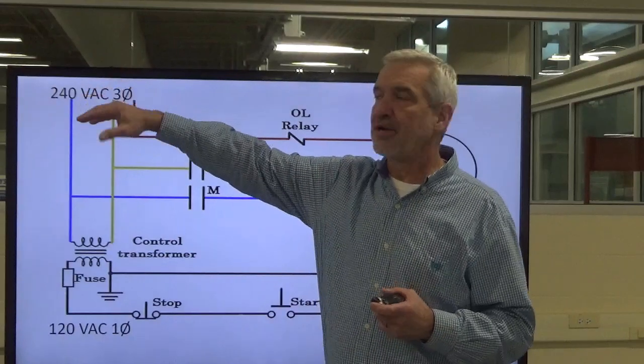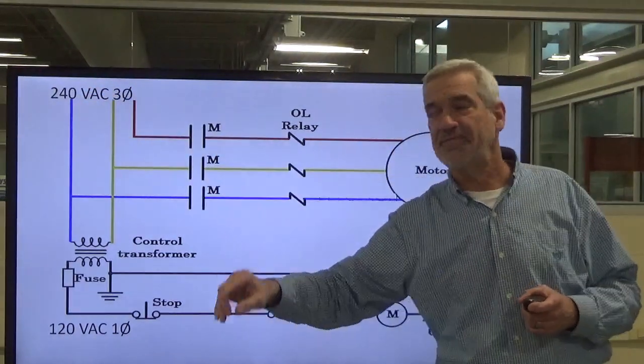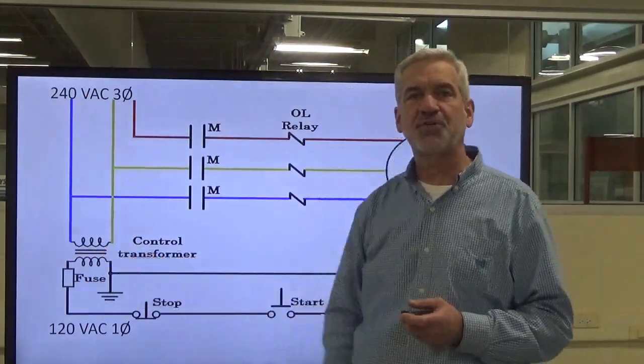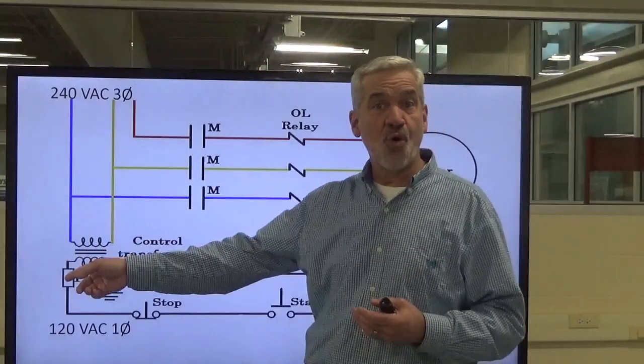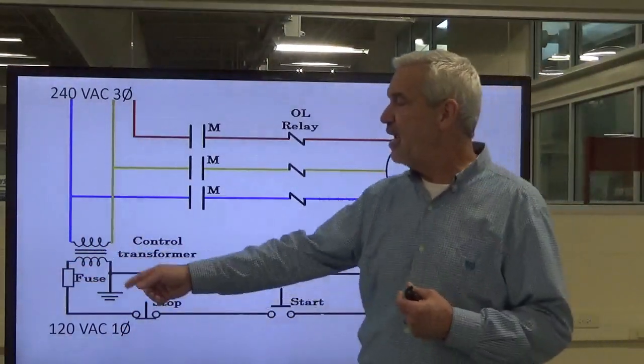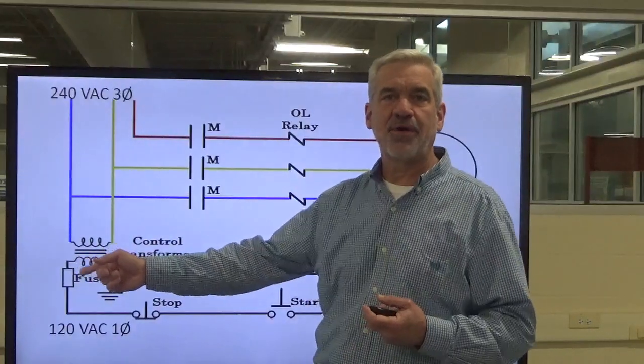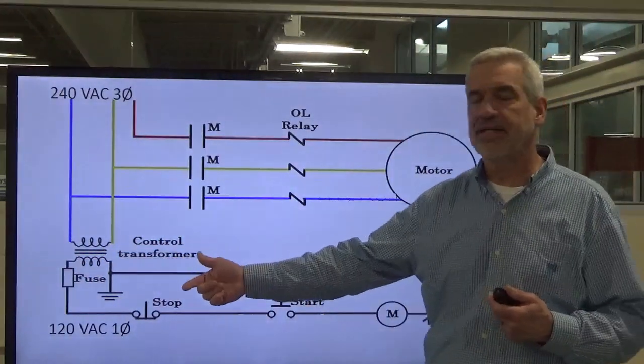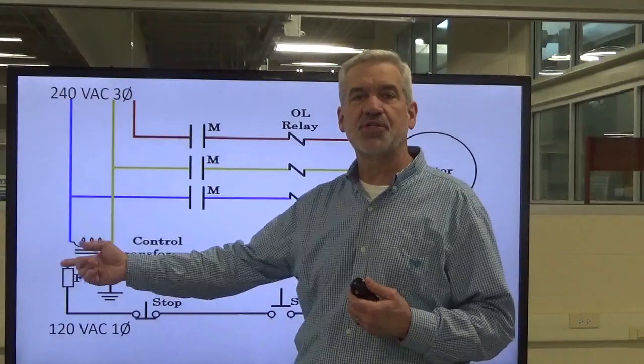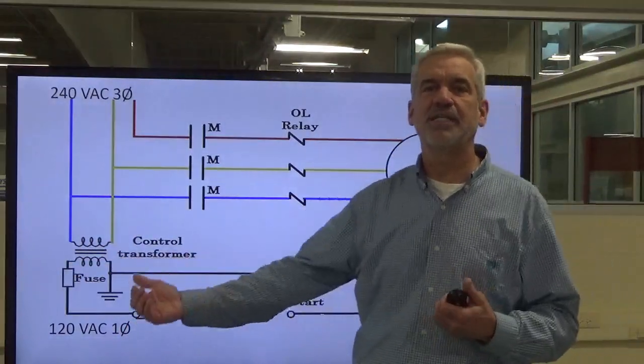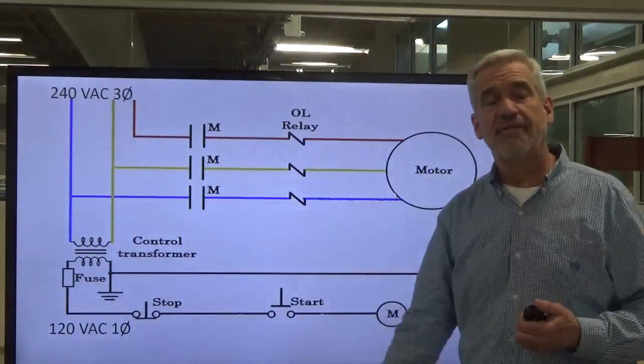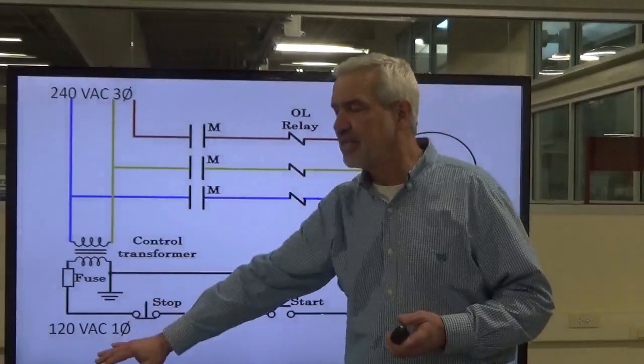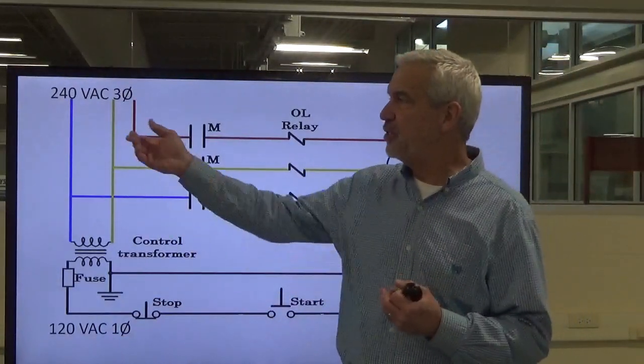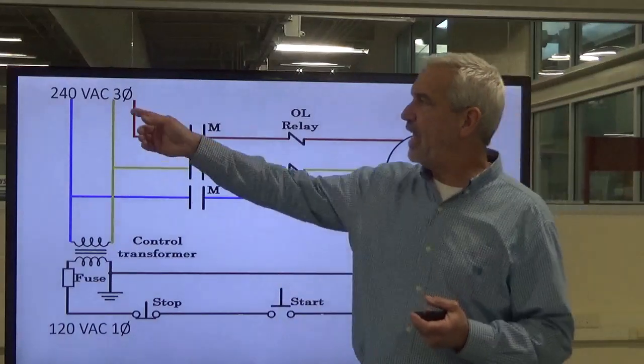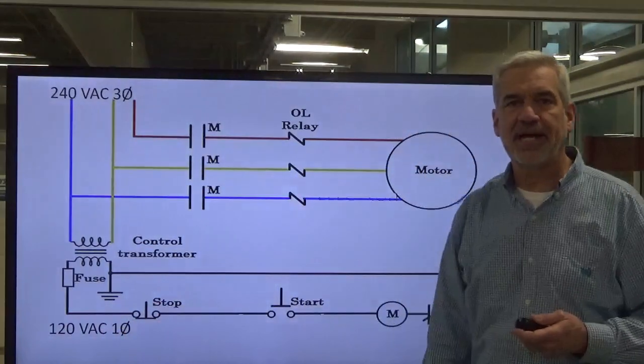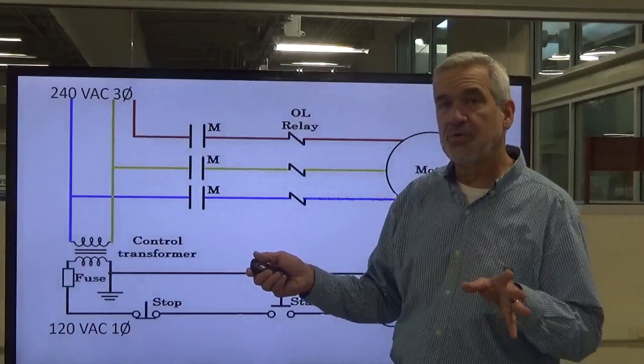3-phase supplied, using 2 legs of that, still single phase, going to the primary coil of our transformer, wrapping around the iron core, the laminated iron core. We have a coil of wire wrapped around the second set of coils, called the secondary, that provides us with a step-down, lower, safer voltage than the 240. In this case, we're stepping it down in half, a 2-to-1 ratio, and we're going to have 120 volts coming out at single phase for our control circuit.